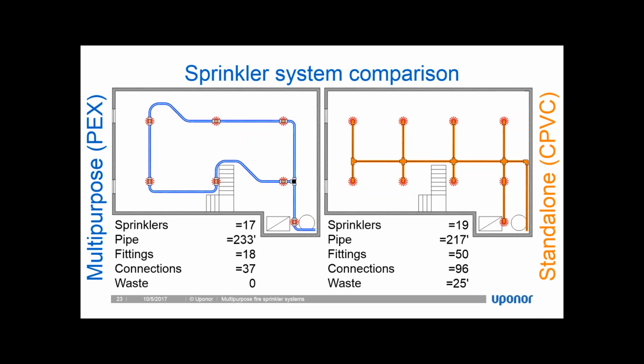I'm up to 217 feet of pipe. I've got 50 fittings, 96 connections. All of those connections could be dry fits, and I've got about 25 feet of waste. So from a total installed perspective, just looking at the sprinklers, we're using more pipe on the Aquapex system, and that's mainly because we have to pipe it in a loop, and we're using less pipe on the CPVC side. But when we factor in waste, it actually becomes more pipe, and the material involved in those fittings and connections really does put it over the top.